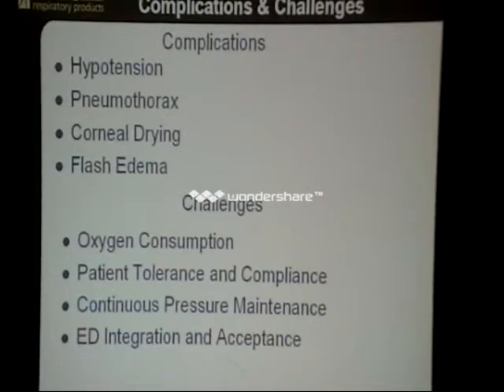Complications. I mentioned hypotension. It will drop blood pressure. You could cause a pneumothorax with it, so monitor your pressures on there. This particular device that you guys went with has a pop-off built inside of the system, so you don't have to worry about, say, that regulator breaks, starts kicking out 300 PSI, it's not going to go to the patient. It's a built-in safety. Corneal drying is just a product of, if you don't have a good solid seal on the mask, oxygen will start leaking into the eyes, and it burns. Oxygen is a drying agent.